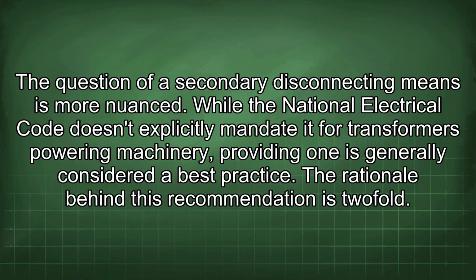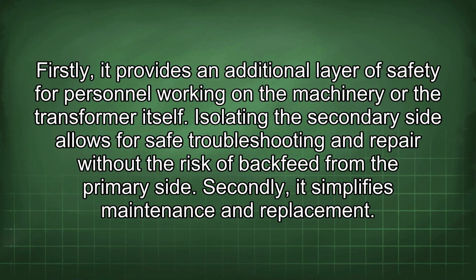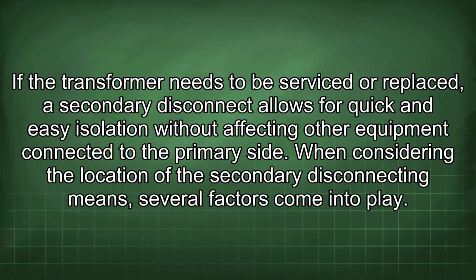The question of a secondary disconnecting means is more nuanced. While the National Electrical Code doesn't explicitly mandate it for transformers powering machinery, providing one is generally considered a best practice. The rationale behind this recommendation is twofold. Firstly, it provides an additional layer of safety for personnel working on the machinery or the transformer itself. Isolating the secondary side allows for safe troubleshooting and repair without the risk of backfeed from the primary side. Secondly, it simplifies maintenance and replacement. If the transformer needs to be serviced or replaced, a secondary disconnect allows for quick and easy isolation without affecting other equipment connected to the primary side.